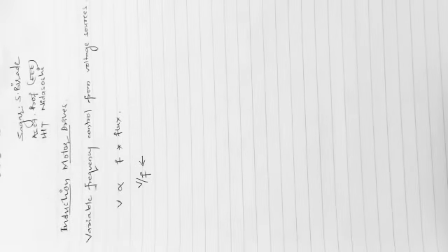We should also note that an increase in flux beyond the rated value leads to saturation of the motor. Also, a decrease in flux is avoided to retain the torque capability of the motor. Therefore, variable frequency control below the rated frequency is generally carried out at rated air gap flux, by consequently varying the terminal voltage with frequency, which maintains the V by F ratio. This should be maintained constant at the rated value.